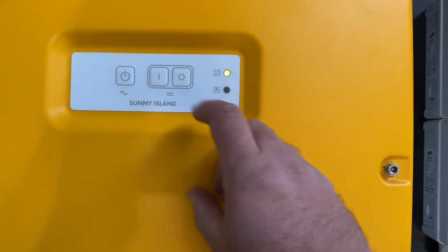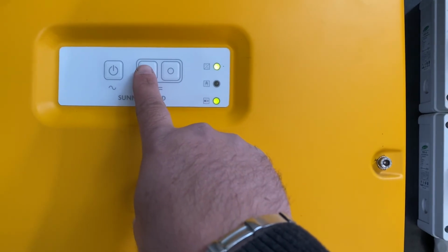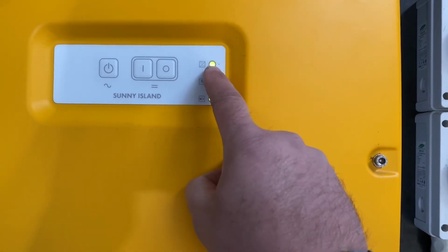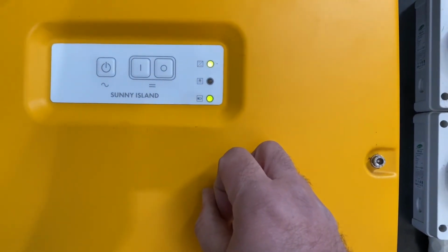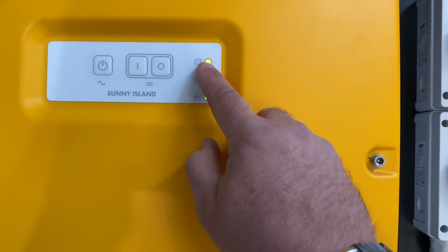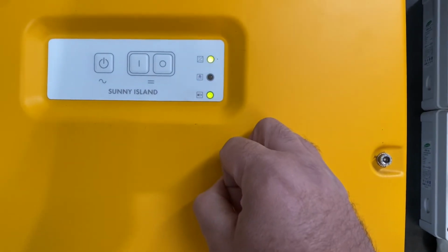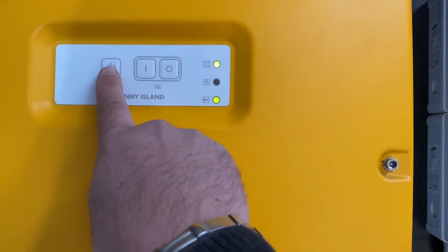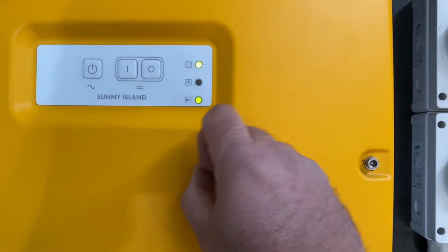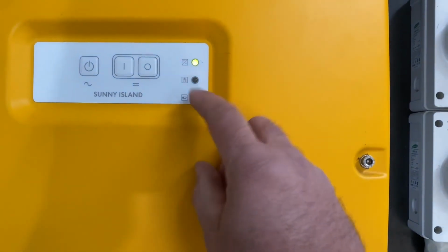So just to reiterate, no lights means the system is totally off. A 3-second press of the DC on button, you will have system lights. Power light will be amber. Wait approximately 30 seconds. Long press of the AC on button and the AC light will turn green and power has resumed. Shutting down, long press of the AC button and system light will turn amber. 3-second press of the DC off button and the system is totally shut down.